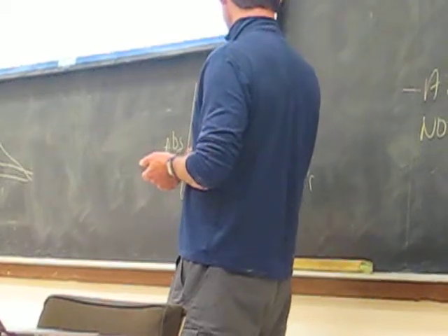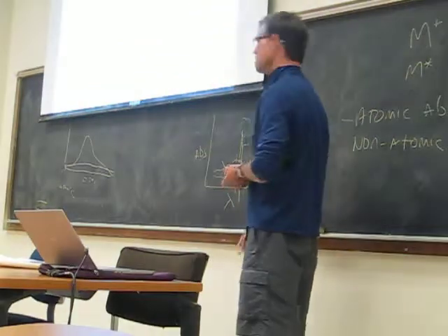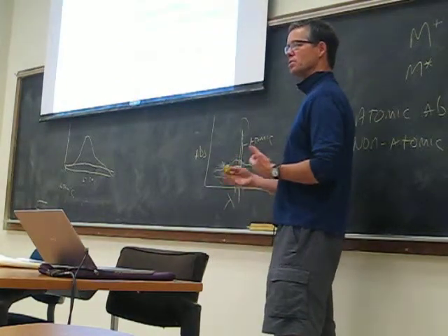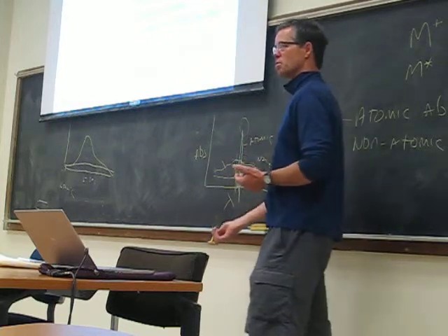And so many instruments, not yours, but many more expensive instruments, have the means to measure absorbance that is attributed to the atomic absorption signal that we want, and have the means to measure absorbance that's being attributed to a non-atomic absorbance signal, which is the background, and to subtract those two to determine how much is really atomic absorbance.